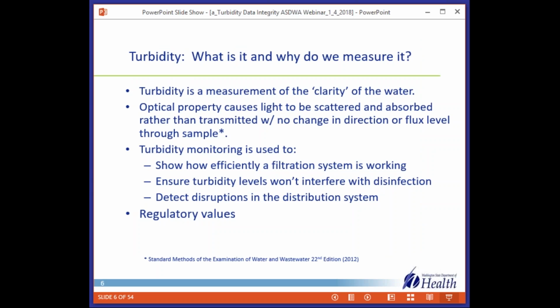If we turn to one of the guiding books or our Bibles in the industry, Standard Methods, turbidity is defined as the optical property that causes light to be scattered and absorbed rather than transmitted with no change in direction or flux level through the sample. Turbidimeters with scattered light detectors located at 90 degrees to the incident light beam are called nephelometers, and results are expressed in nephelometric turbidity units, or NTUs.